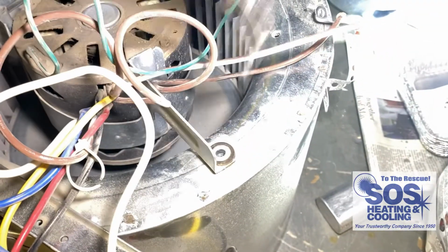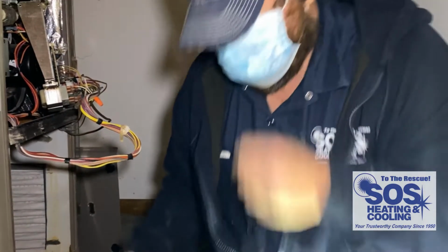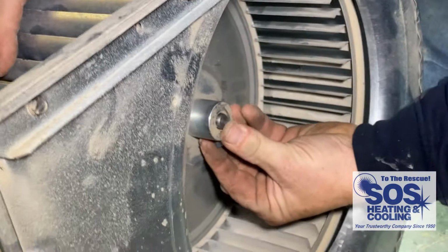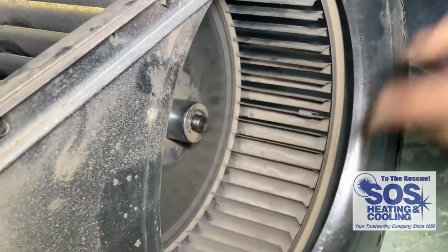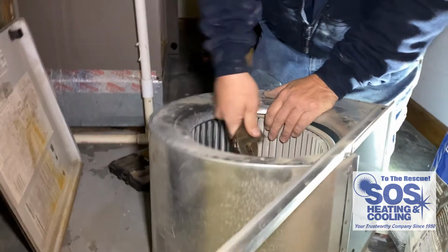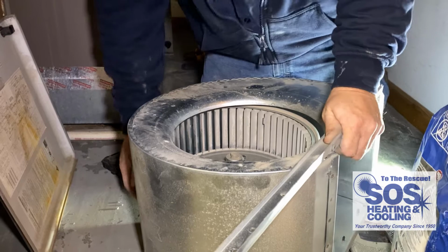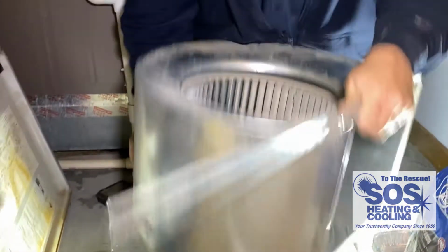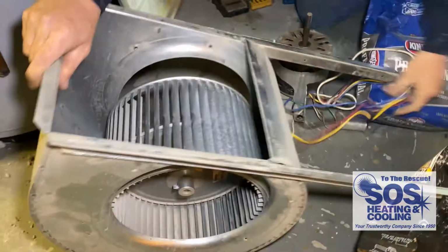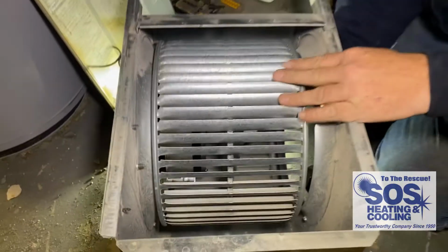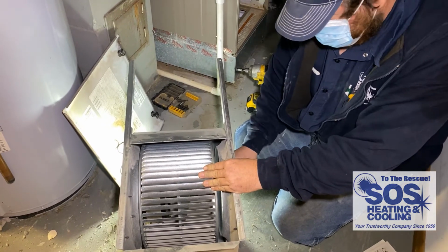In this scenario, this is the reason why the furnace didn't turn on, because I didn't have the blower motor running. The blower motor provides air throughout the duct system, the delivery system of the furnace. Very important, just like anything else. Without that piece, what will happen is the unit will limit. It won't supply proper airflow to the ductwork, to the rooms that need the extra heat or the cool. So we use this in heating and cooling.